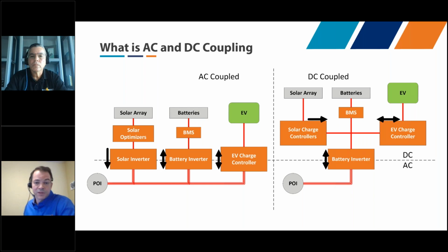On the right-hand side of this diagram, we've got a DC coupled system. You can see it's the same sources and loads, solar array, battery, and electric vehicle, but now all of those are connected on the DC side. You've got a solar charge controller hooked to the DC bus, the EV charge controller is a DC-DC converter, and the batteries and BMS are hooked directly. You've then got one single power conversion equipment that does the AC to DC to AC conversion, and that of course is bidirectional. So that just defines the terms of what we're talking about today between AC coupled and DC coupled.